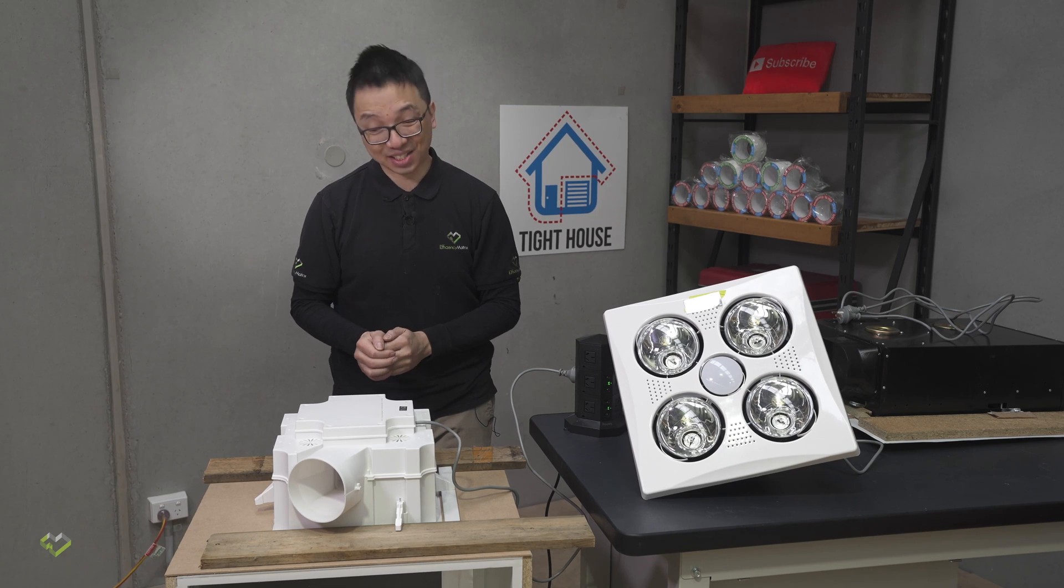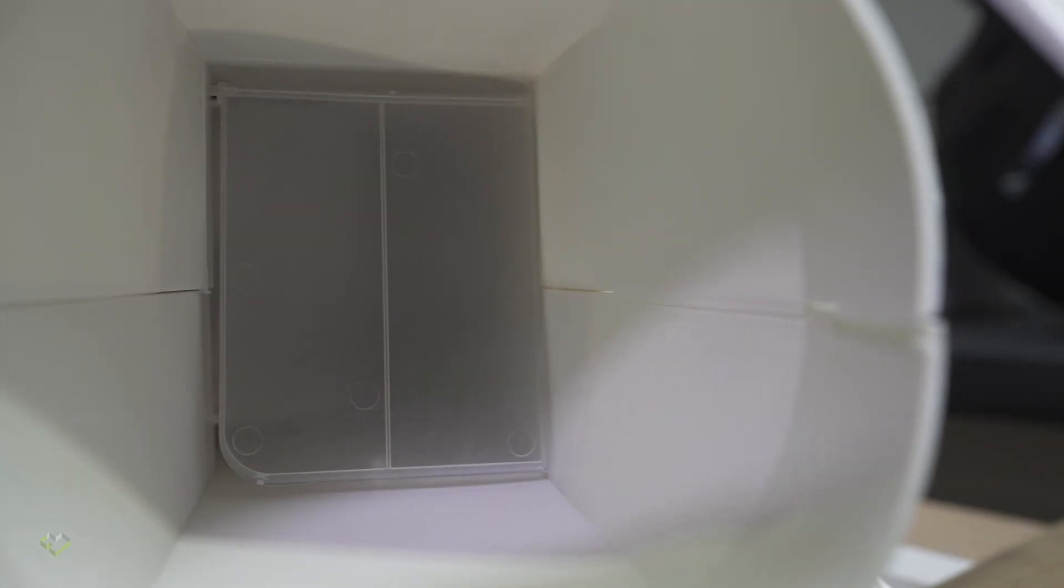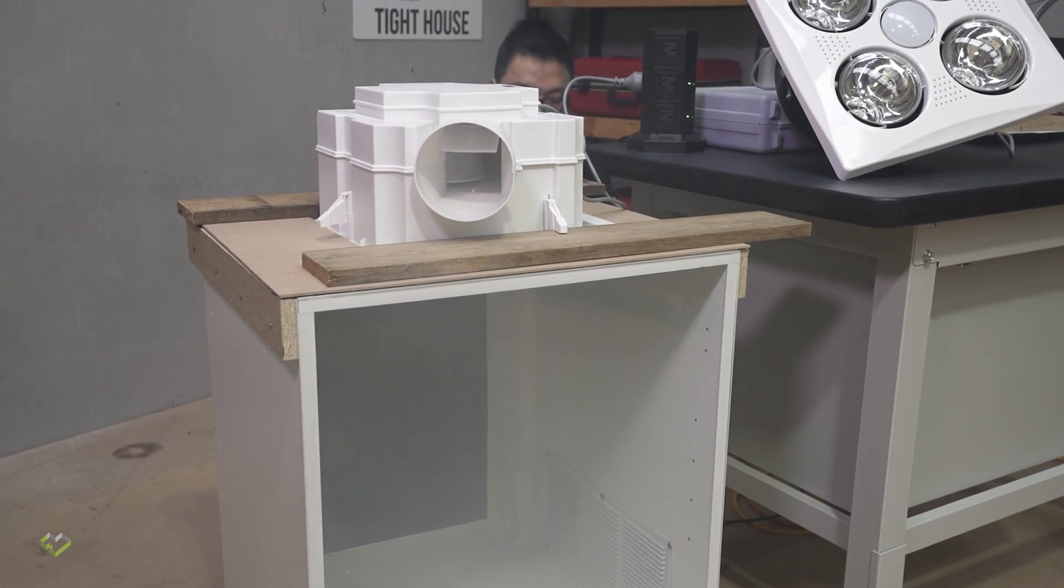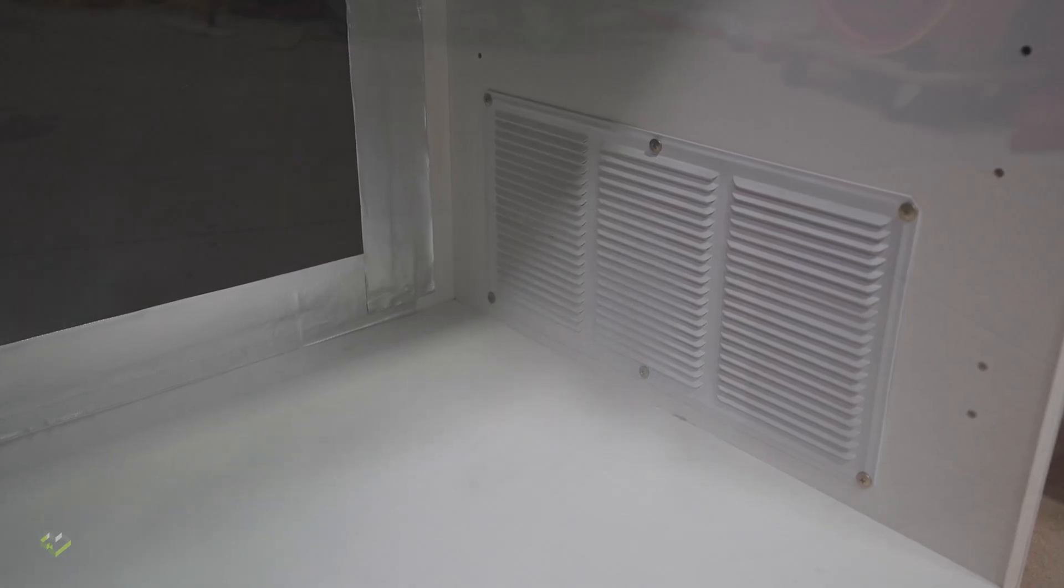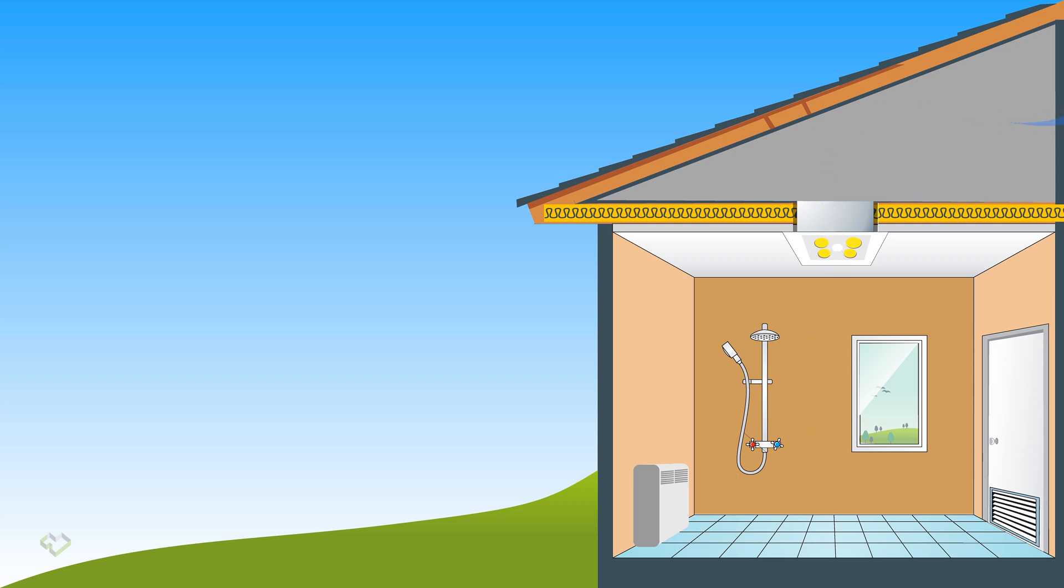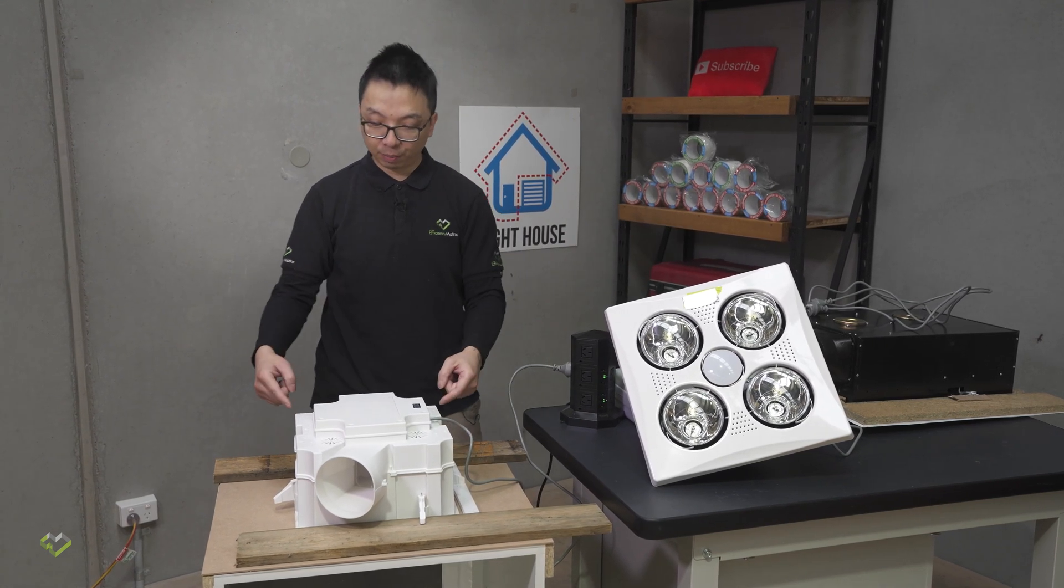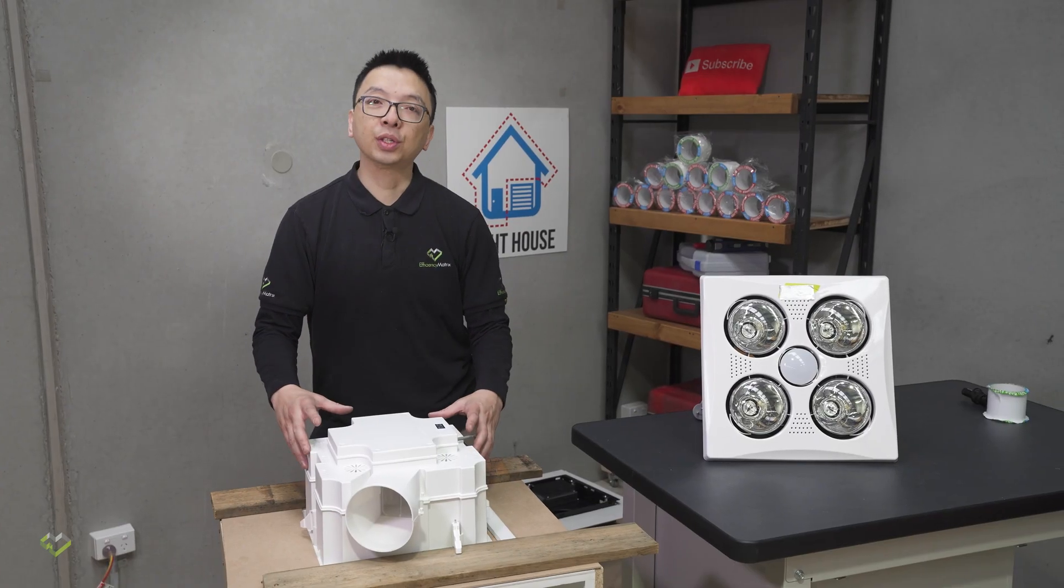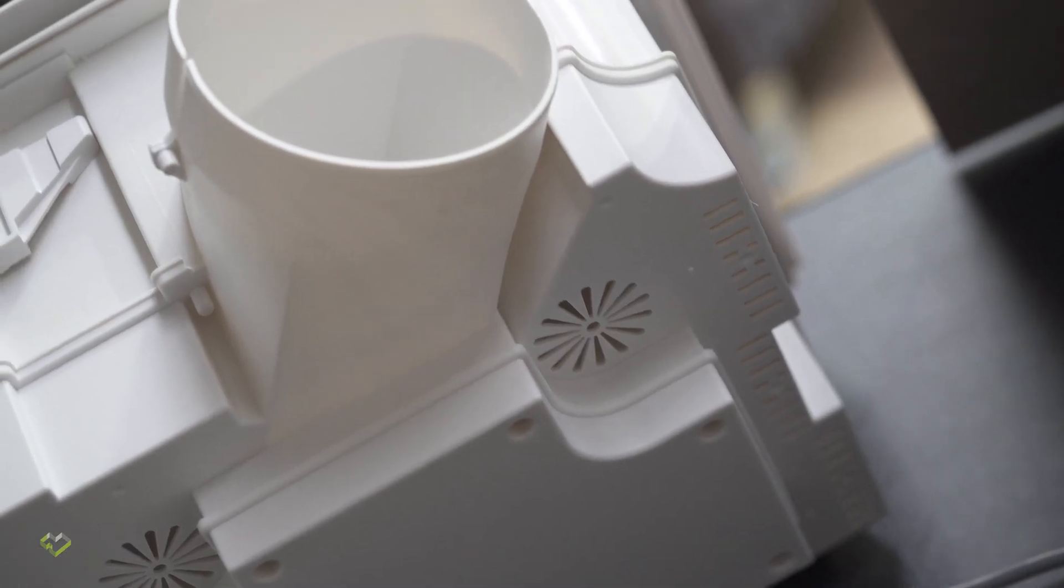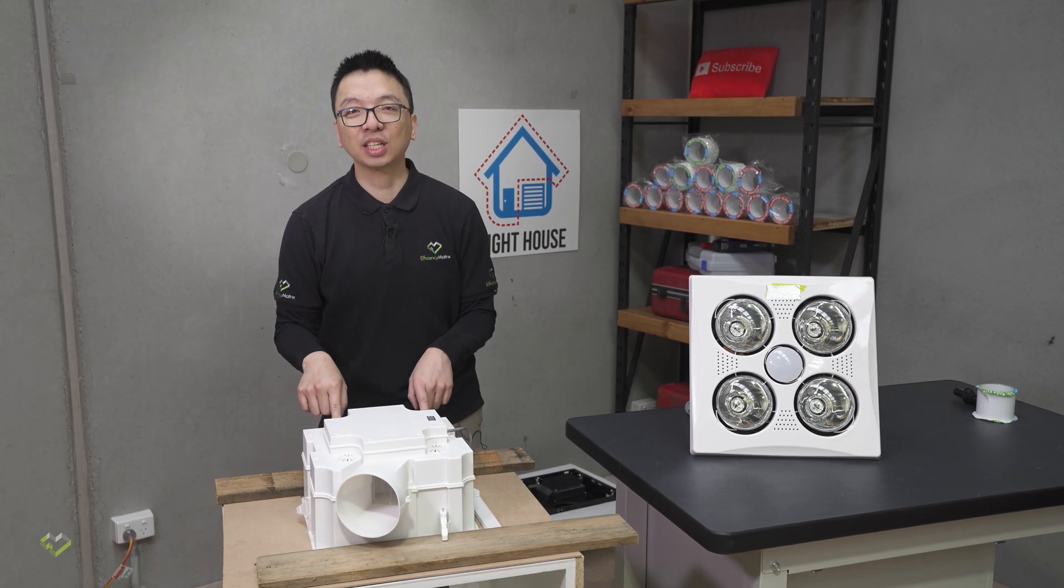So it's not really a very clever and nice solution. Just like the previous video we talked about the exhaust fan, all these exhaust units need to have sufficient inlet for the air to come into the bathroom for the unit to draw out. For this particular unit or this type of unit, because if you don't get enough opening as an inlet to get air into the bathroom, it will not increase the pressure inside your bathroom to draw more air in. All it will do is instead of drawing air from other area into the bathroom, it will just recirculate the air in the roof space which is a waste of energy and it also sharply reduce the effectiveness of the ventilation. That's something we all need to bear in mind. For this unit we did some measurement using a high sensitive flow hood that measure airflow. It's up to 40 percent of the air that the exhaust fan is pumping out coming from the ceiling space.